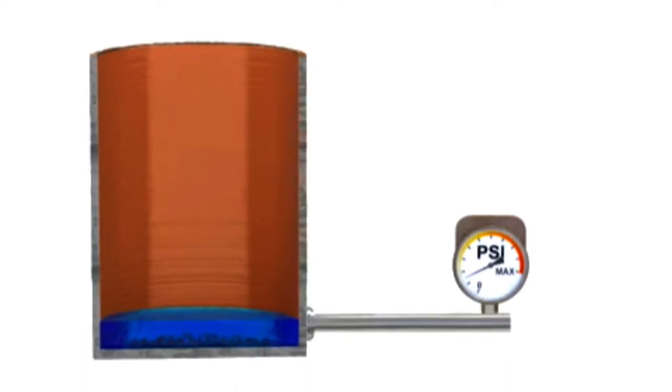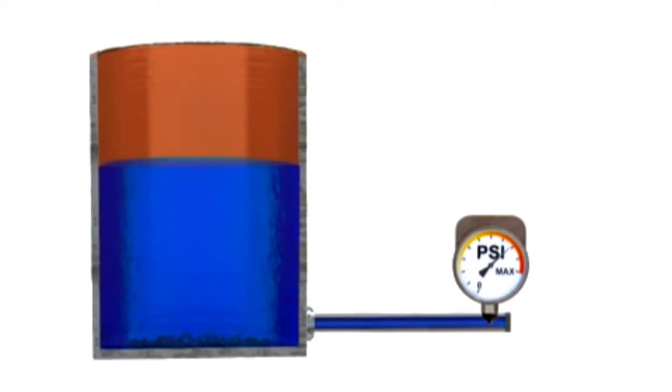The pressure exerted by a fluid material in a vessel is directly proportional to its height multiplied by its density. Hydrostatic pressure or head pressure is the force produced by a column of material. As the height of the material changes, there is proportional change in pressure.